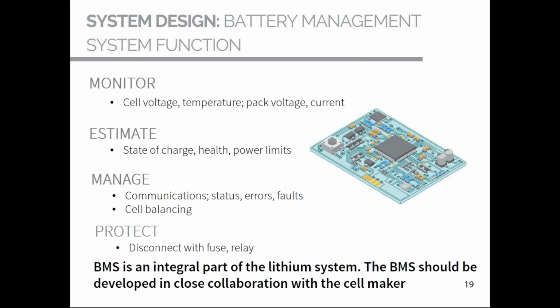Finally, and probably most importantly, the BMS must be able to protect the cells by electrically disconnecting them from the system. If the BMS isn't able to keep the pack in a safe operating range by controlling or communicating with other devices, its last line of defense is simply to disconnect from the system.